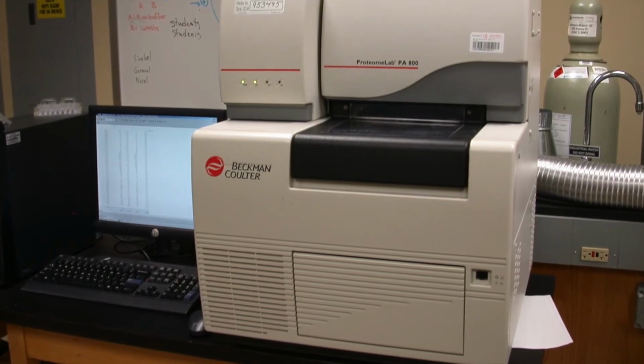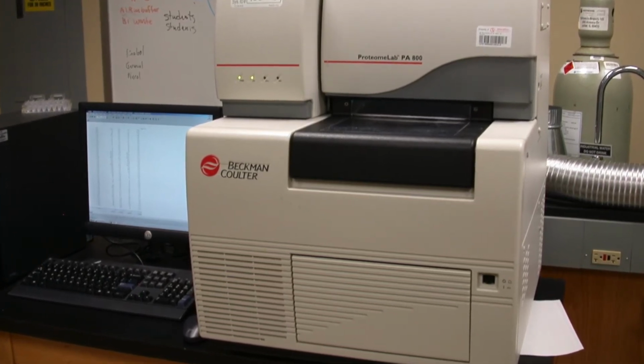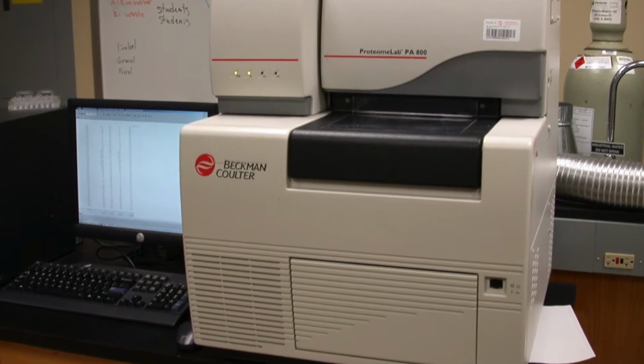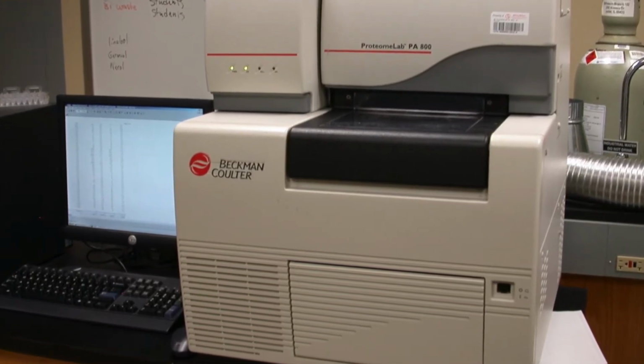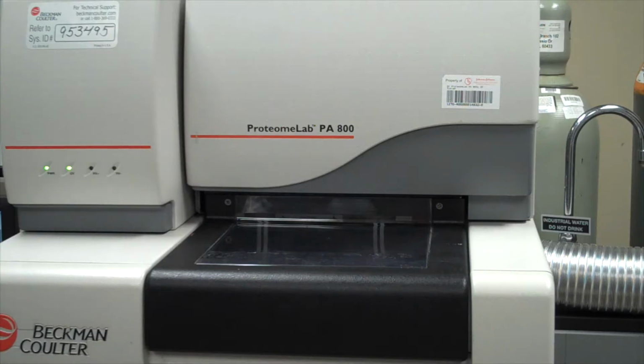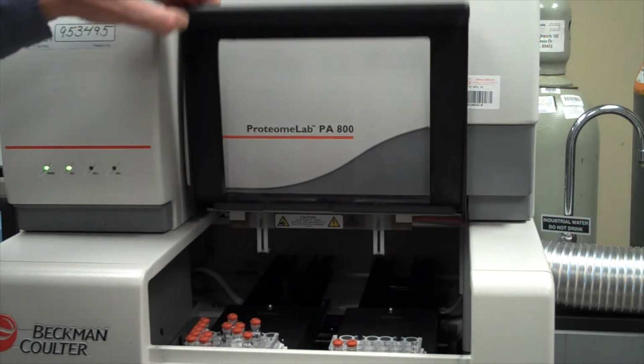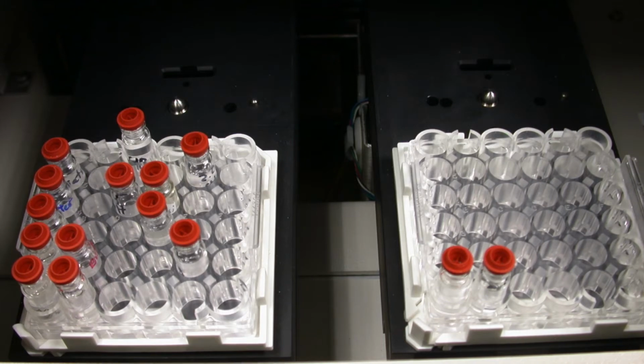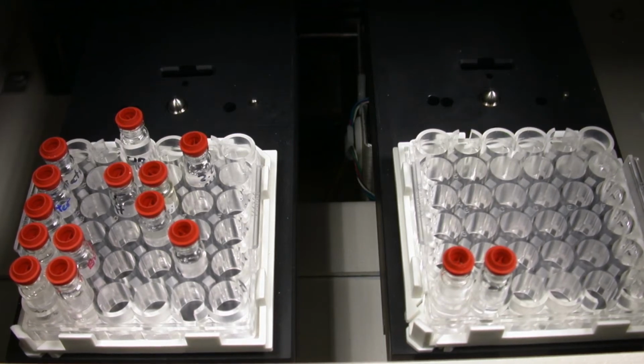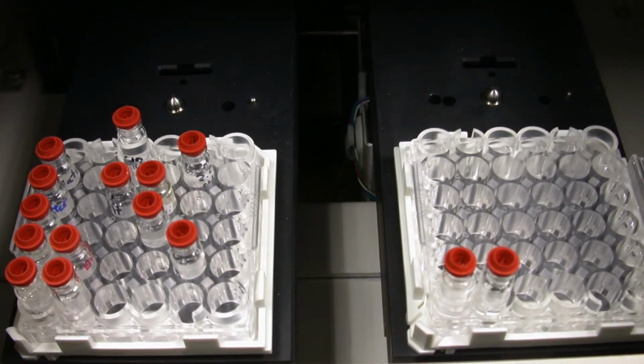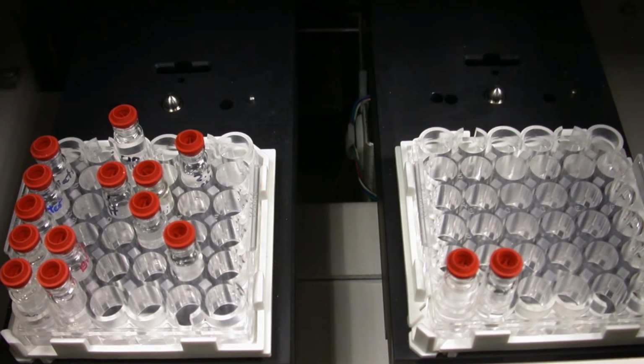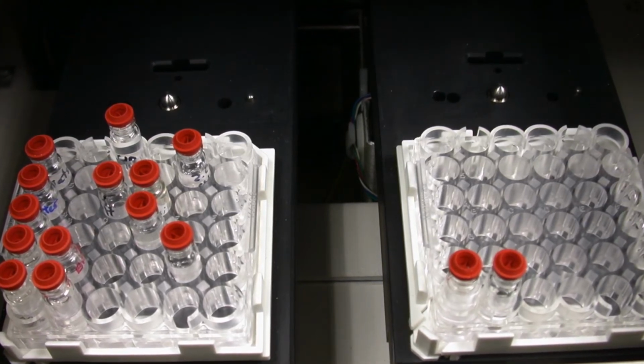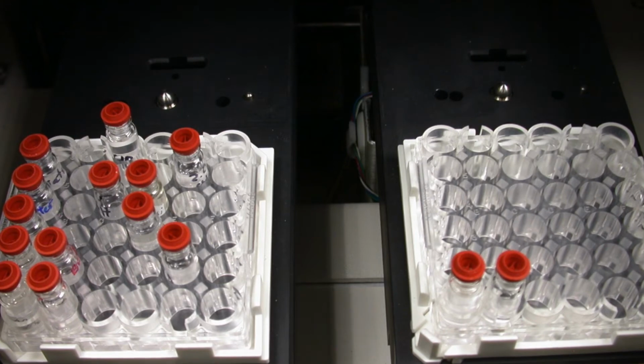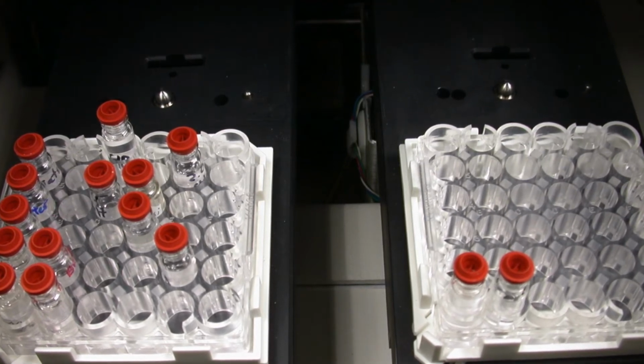This video covers the standard operating procedure for the Beckman Coulter PA800 capillary electrophoresis instrument. The heart of the instrument is accessible through this dark cover. The standard solutions and the running buffer that is used to fill the capillary are held in small vials that are organized into trays. The tray on the left holds vials that are used to introduce samples and various rinsing solutions at the inlet side of the capillary.